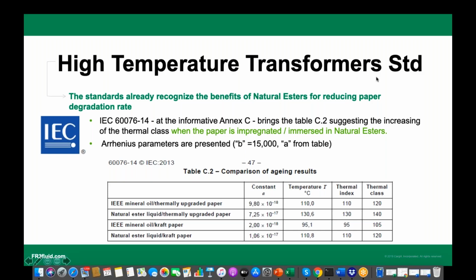And when you go to that temperature, the limitation is the fluid, which is mineral oil, and the limitation of the conductor sometimes becomes, from the short circuit point of view, aluminum. So when you have that type of opportunity, that type of thinking way forward, then the choice always becomes between the natural ester and copper wound transformers. So let's move to the next slide.